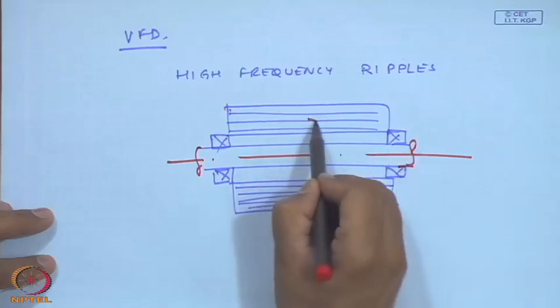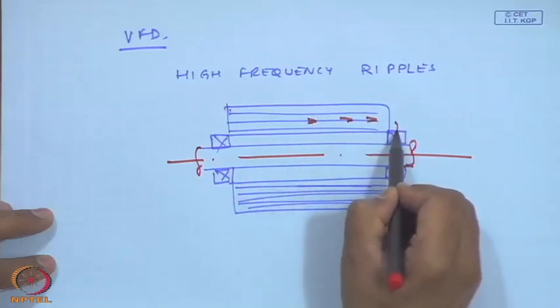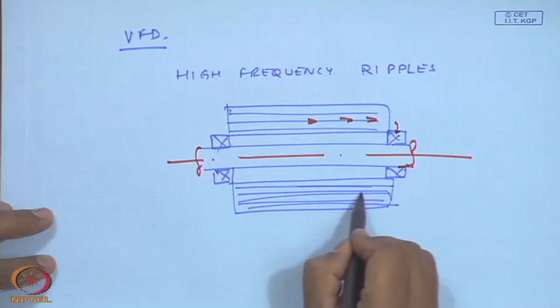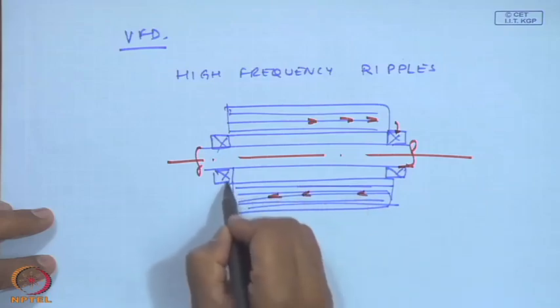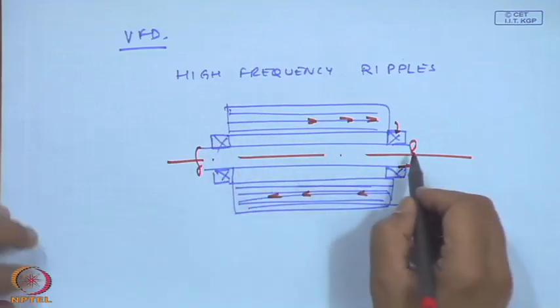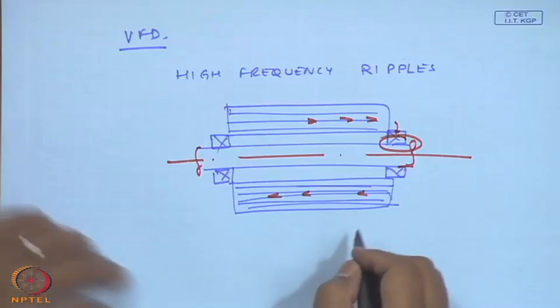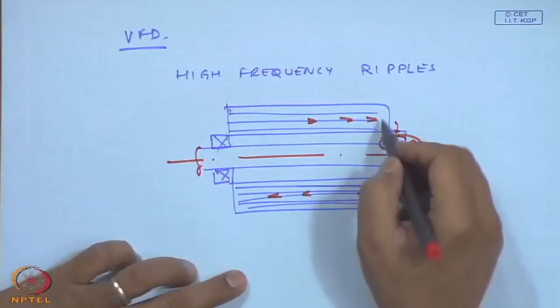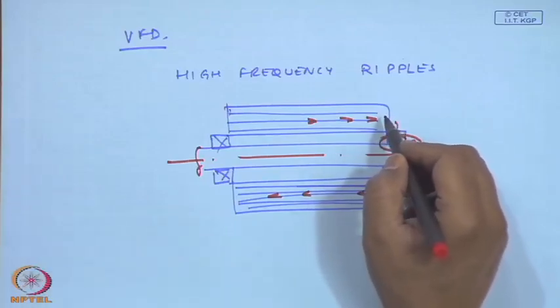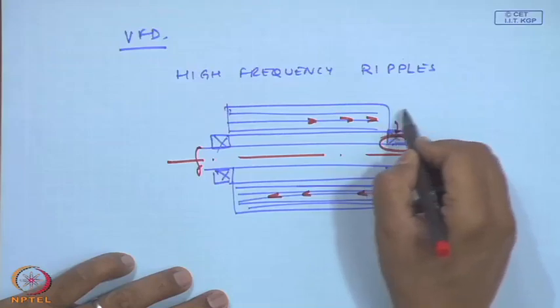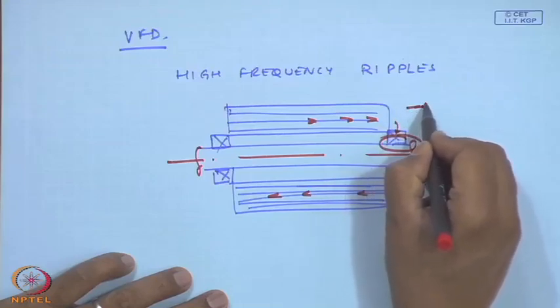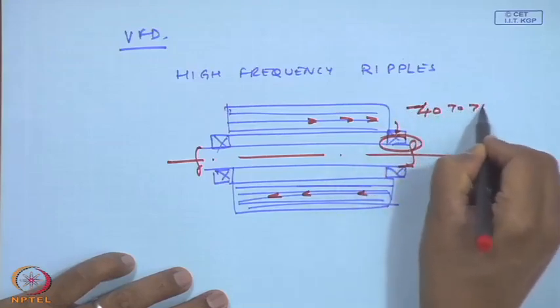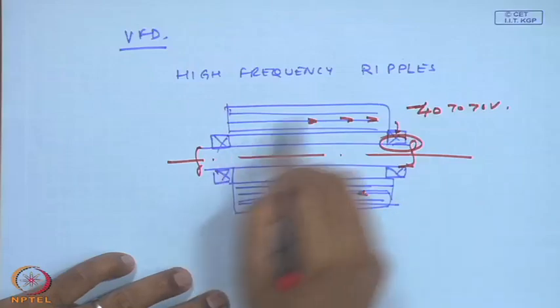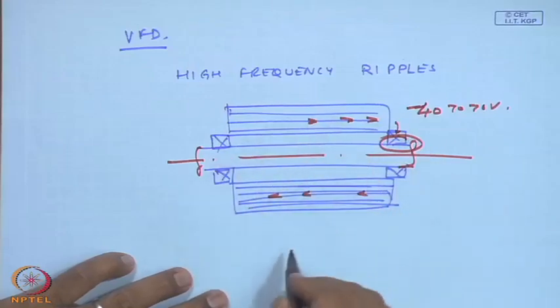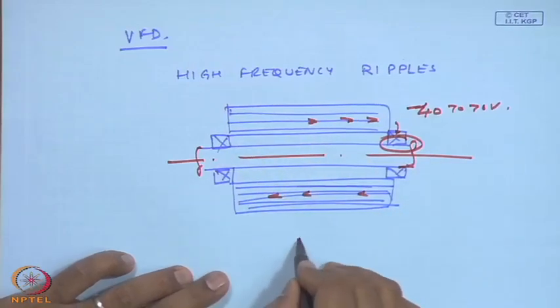What happens? There will be a current flowing in this conductor, which gives a voltage as a loop. And particularly at the bearing, what happens? These are very high frequencies, and they could have voltages of typically about 40 to 70 volts, and they are going in this loop here. What happens at the bearings, if you will see?